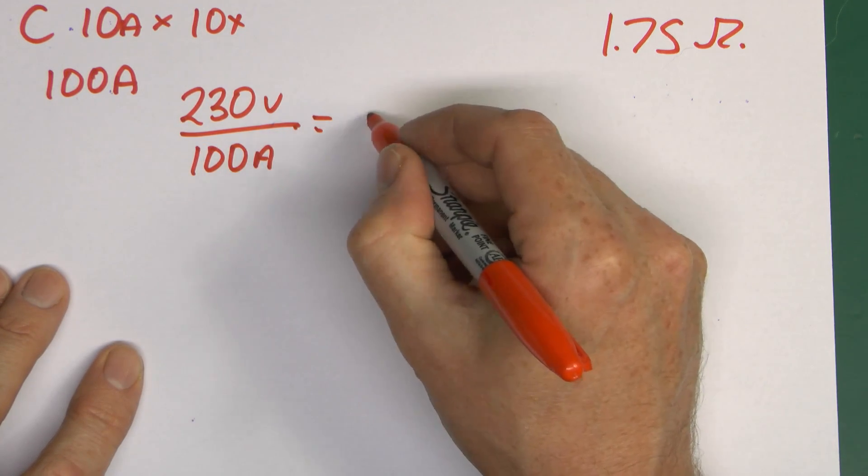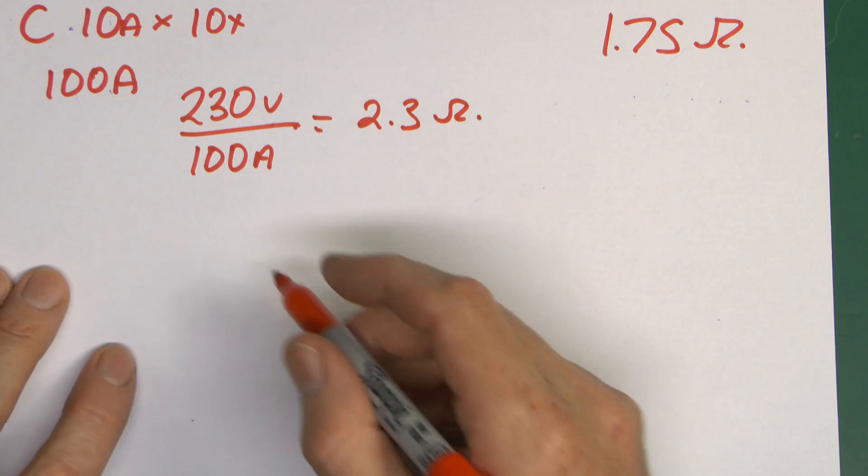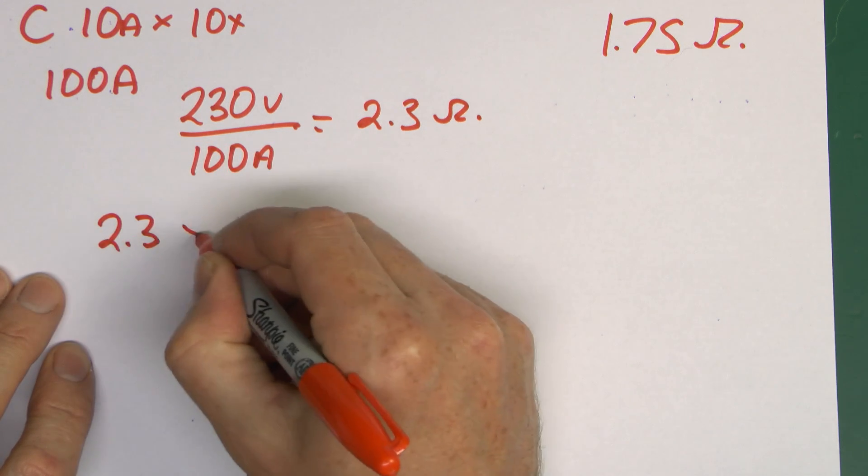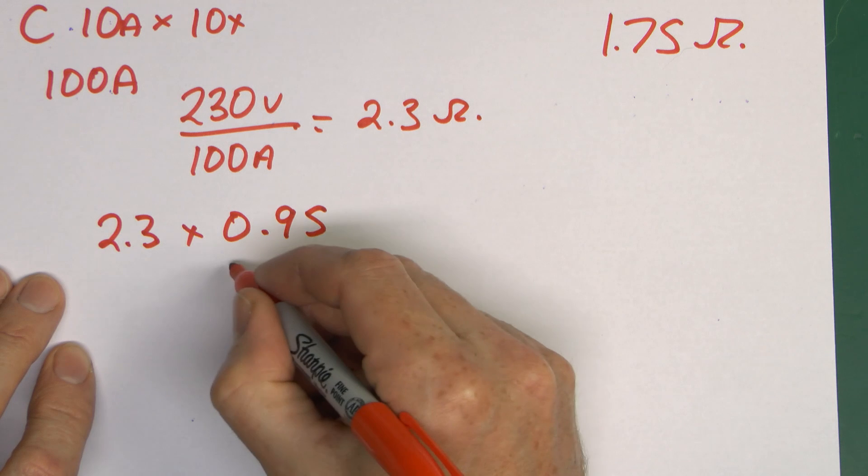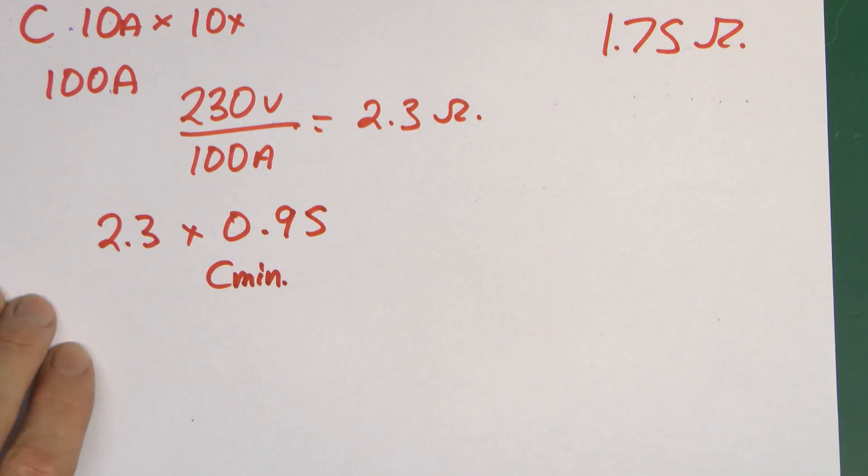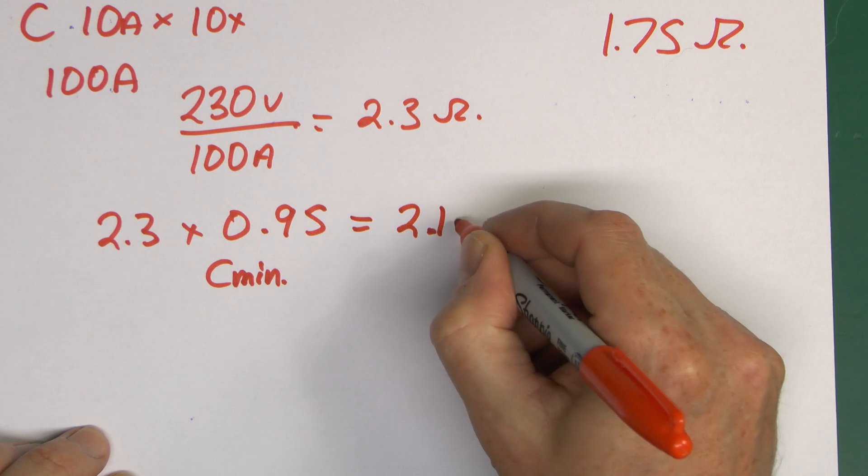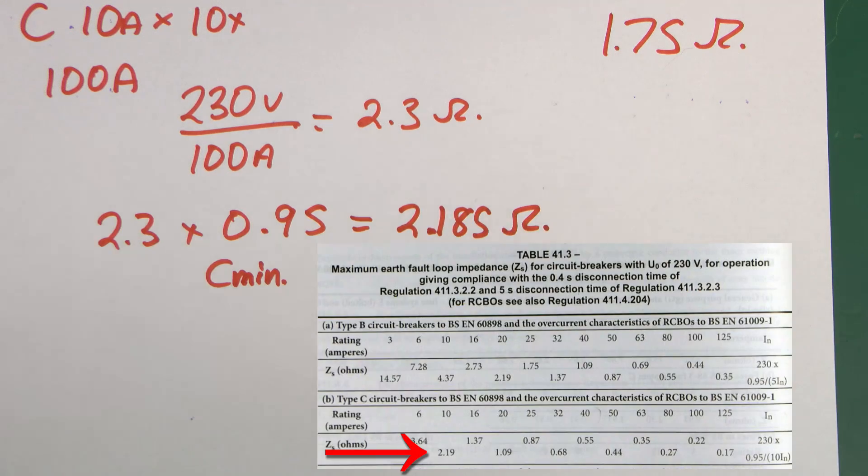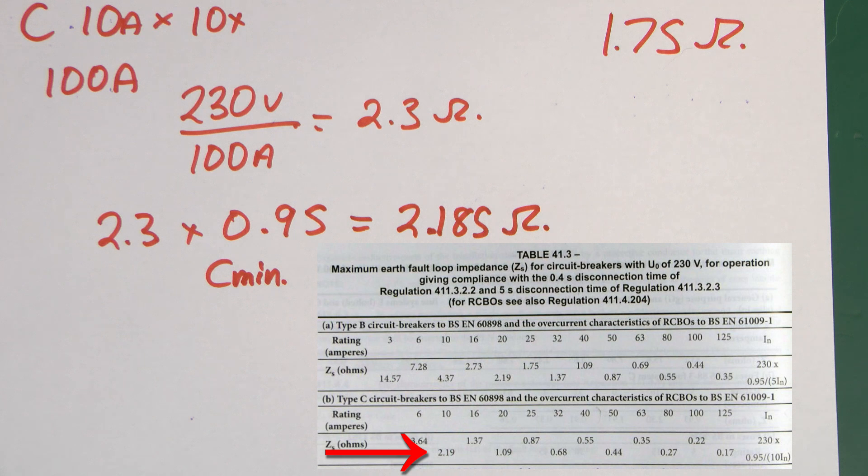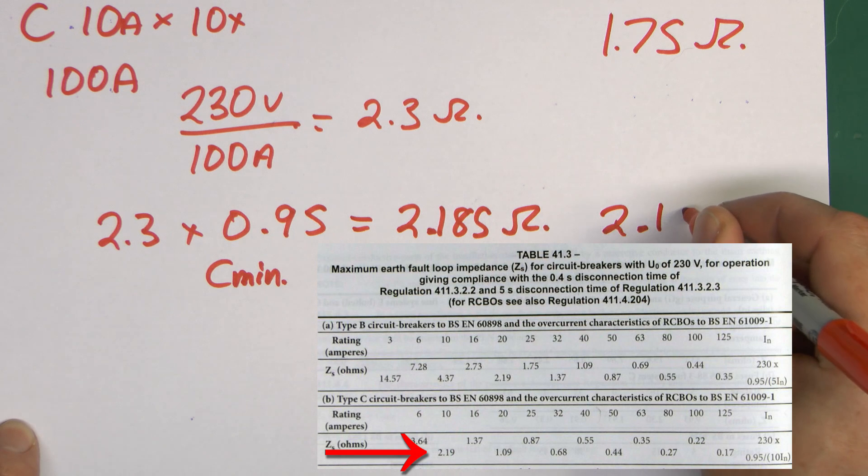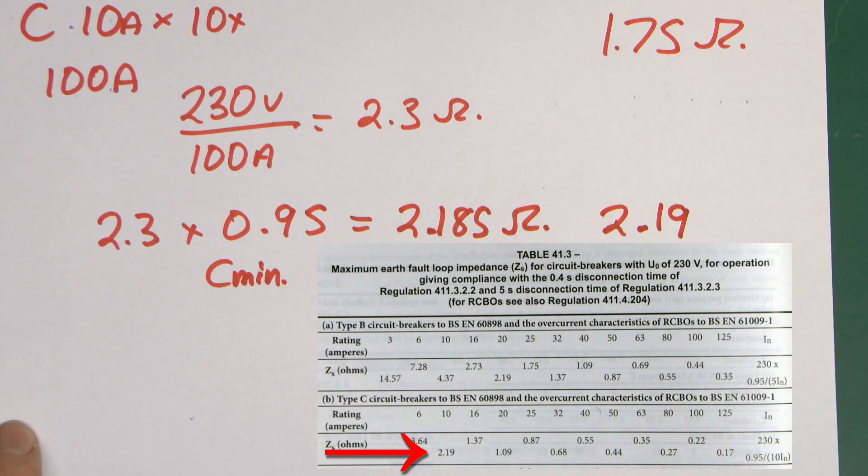And again, the voltage in the UK is of course 230V, so 230V divided by 100A. That will give us a value of 2.3 Ohms. Again, as we had before, there is that correction factor we need to apply, so then it will be 2.3 multiplied by 0.95. So remember that was that Cmin, to account for the possibility that the voltage could be lower than 230. And if we just calculate that one out, we get 2.185. And if we have a look in that table 41.3 in the BS7671, that's basically the value we get there. They've actually got it in there at 2.19. So again, just rounding up to the nearest two digits there.